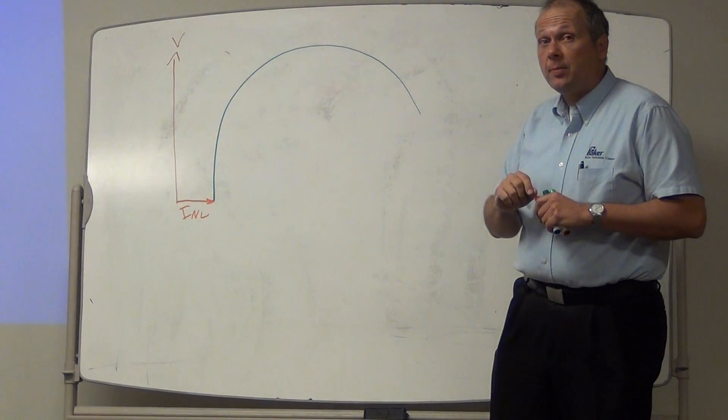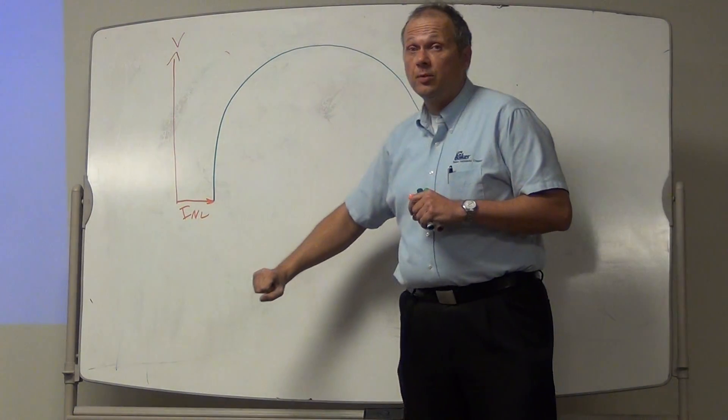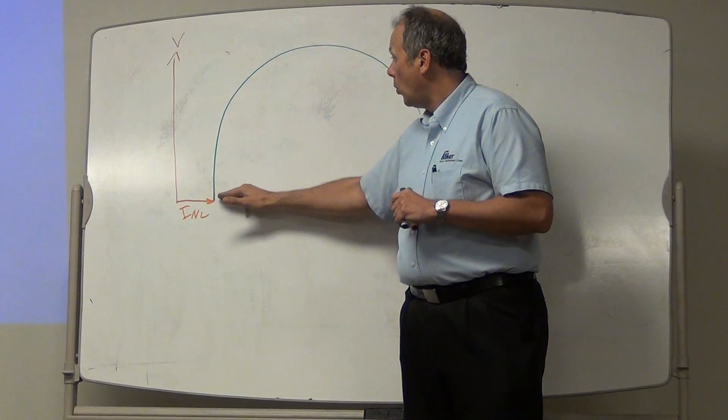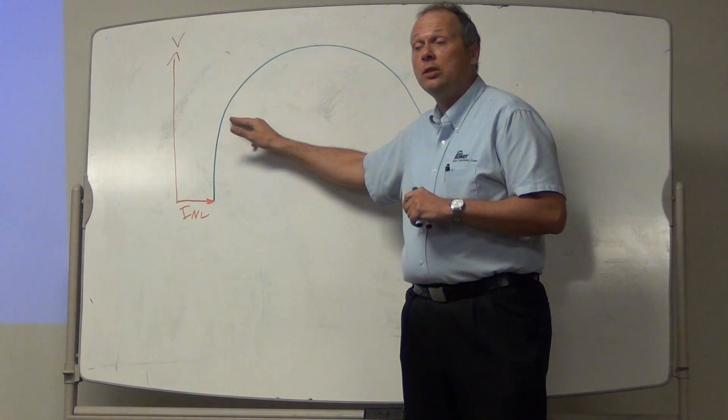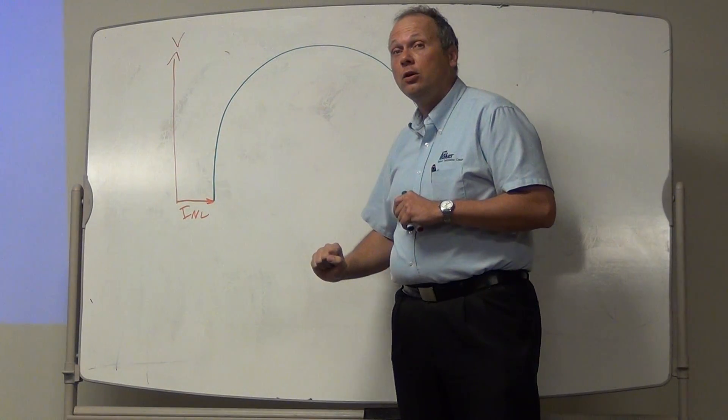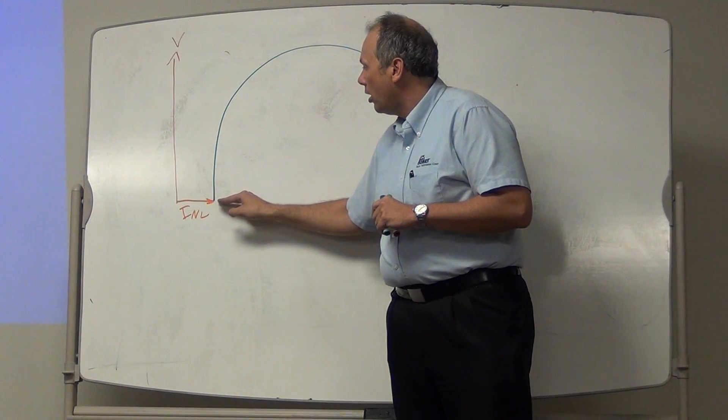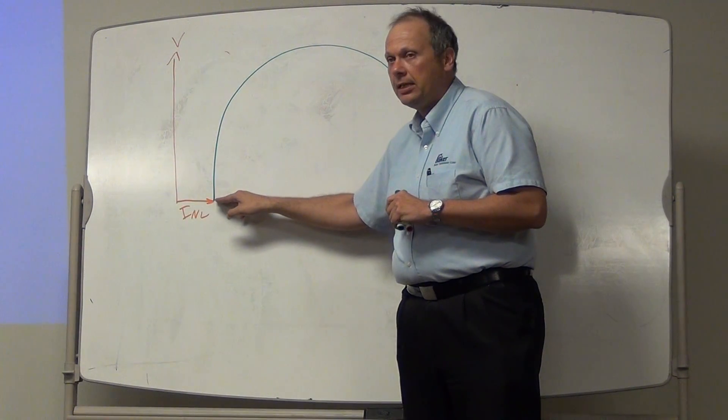The Heyland Circle describes the trajectory upon which the induction motor's current walks as I keep increasing the load. At the no-load point, I throw my shadow over here, no load, there's no power. There needs to be no shadow on my no-load current, so that's why I'm off by 90 degrees.